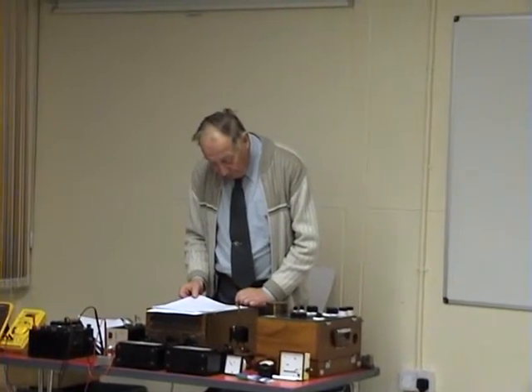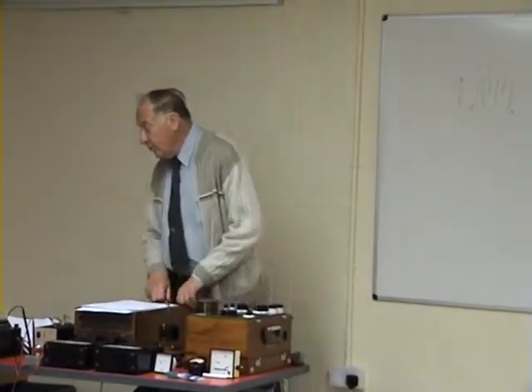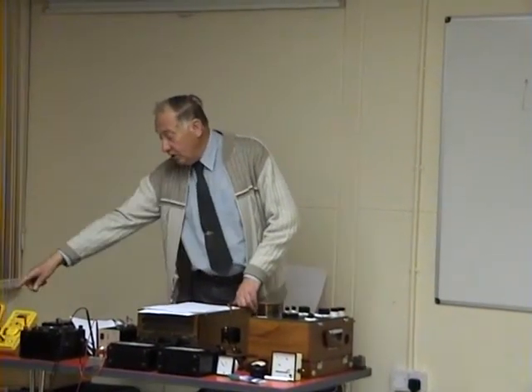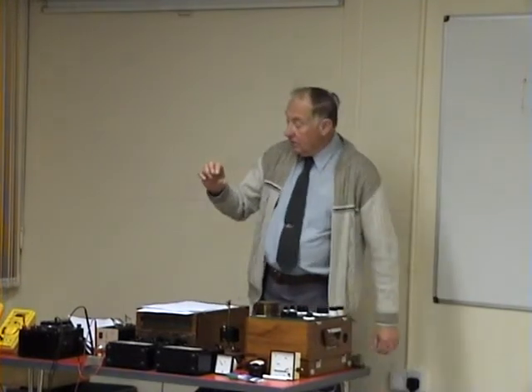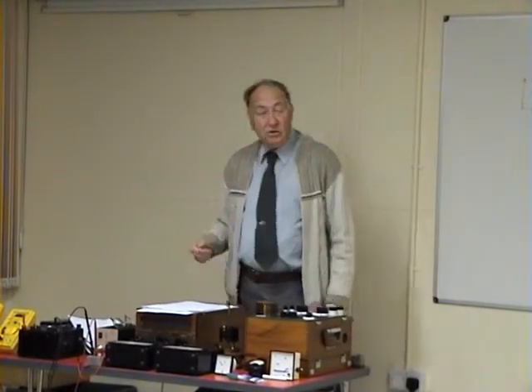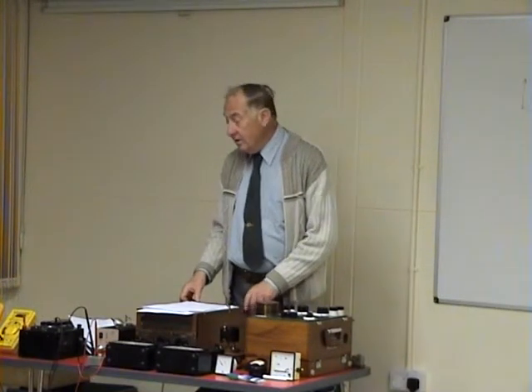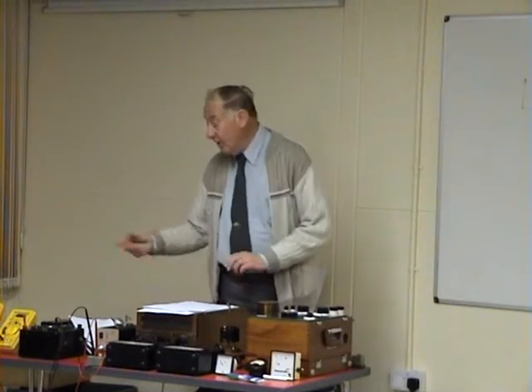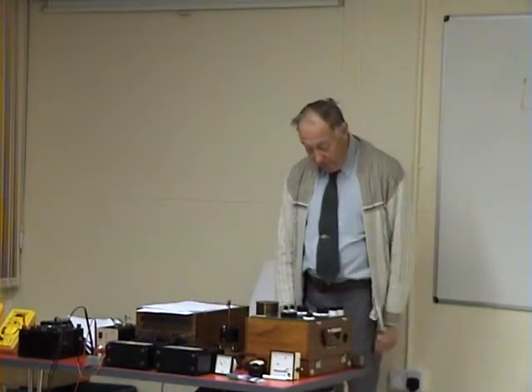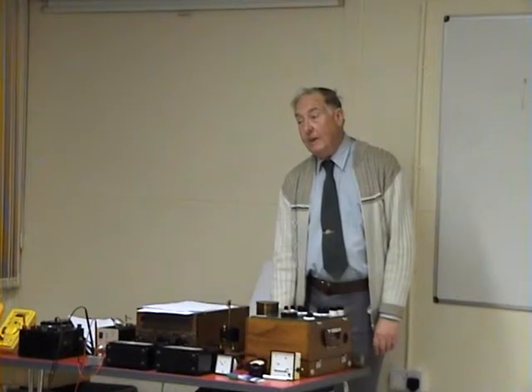That was fusible resistance. Right. If we want to measure big currents, then to measure current in one of these, it's a piece of wire about 1 inch long, and they scrape it to the right resistance, and so the meter reads say 10 amps or 20 amps in this 20 amp range. If you want to measure 100 amps or more, you have to use an external shunt.